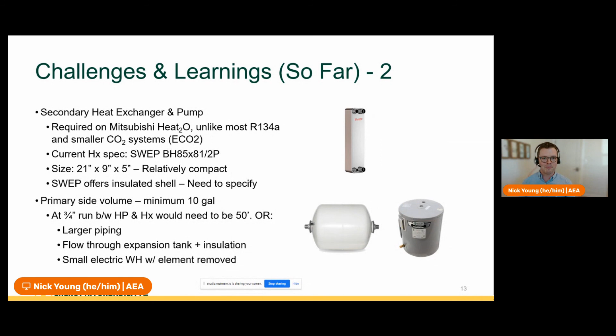So what can you do to get that volume? You could have larger piping, but piping tends to be very expensive. So what we're seeing is projects going with either a flow-through expansion tank that's then insulated, or a real MacGyver solution some projects have found: a small electric water heater with the element removed or not connected. That gives you a small, 10-gallon, fully insulated component that's easy to purchase and relatively cheap, which can get you that volume on the primary side.